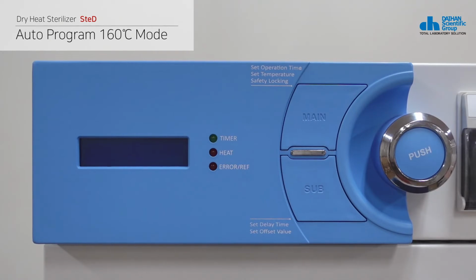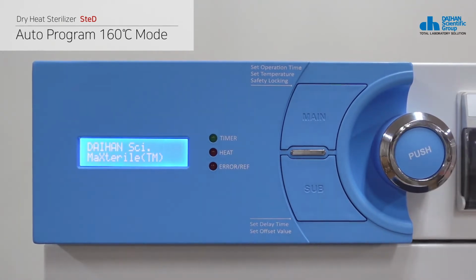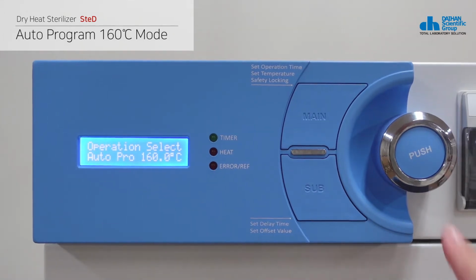Turn on the power switch. The initial screen is the auto program 160 degrees Celsius mode. This mode automatically executes sterilization at 160 degrees Celsius for 60 minutes. In auto program 160 degrees Celsius mode, press the push button to start heating.